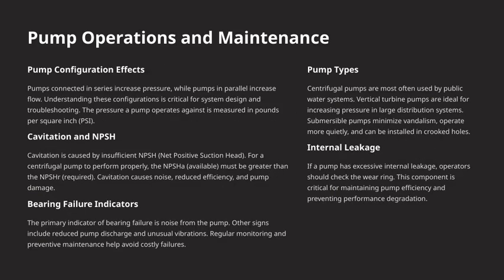Let's talk about pump operations and maintenance. First, the configuration of pumps can significantly impact system performance. Pumps connected in series are used to increase pressure, which is useful when you need to push water over long distances or to higher elevations. On the other hand, pumps in parallel are designed to boost flow rates, providing more volume when needed. Understanding these configurations is essential for designing efficient systems and troubleshooting issues effectively. Remember, the pressure a pump works against is measured in pounds per square inch, or PSI, which helps us monitor and control performance.